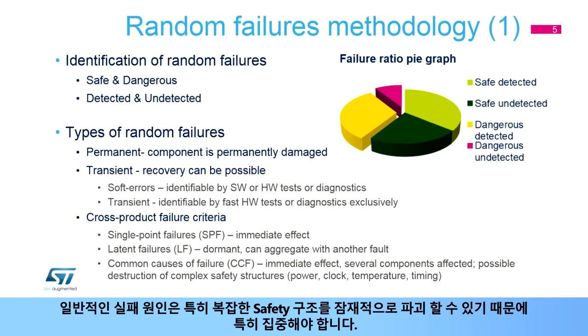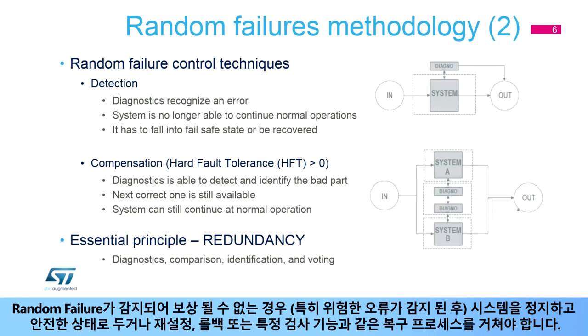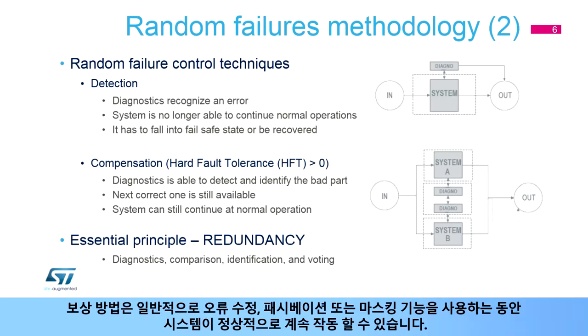When random failures are detected and cannot be compensated for, especially after a dangerous error is detected, the system has to be stopped and placed into a safe state, or go through a recovery process like reset, rollback, or a specific check function. Compensation methods usually allow the system to continue operating normally, while using error correction, passivation, or masking functions.